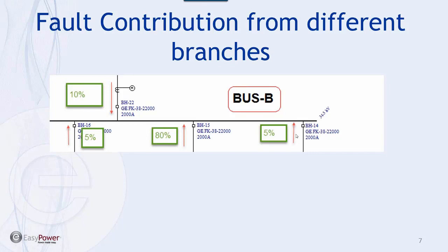And then I can use that value to calculate the trip device times. I covered it before. This is one method; there are other methods. Once you have the arcing current on the bus, then maybe you can look at the impedance values of all the branches and, as you put a current source here, use some of the common methods in power systems and calculate the contribution from each branch. That could be another option.